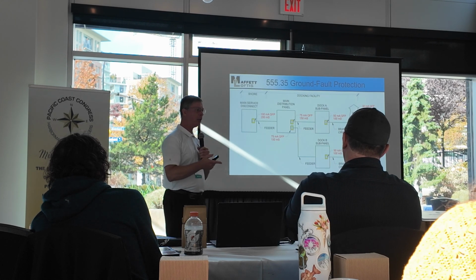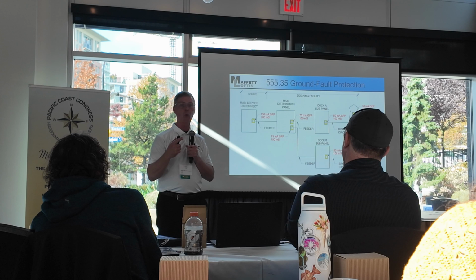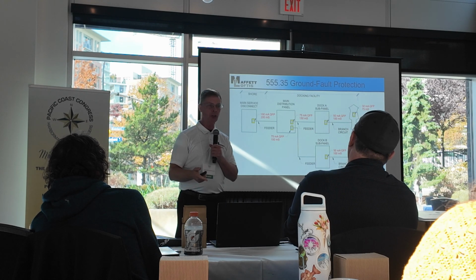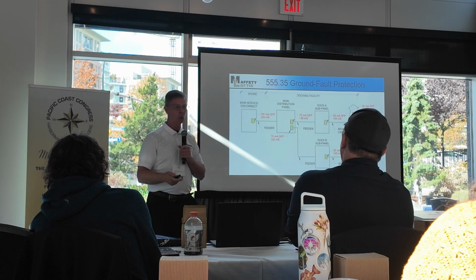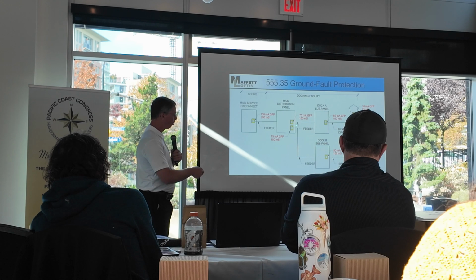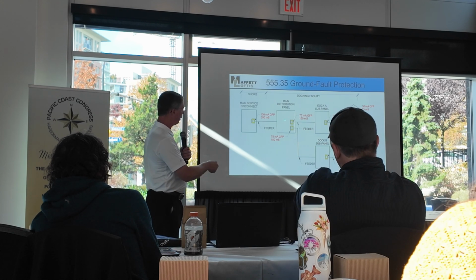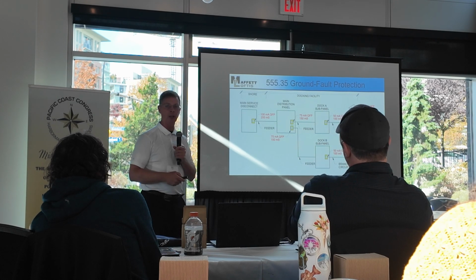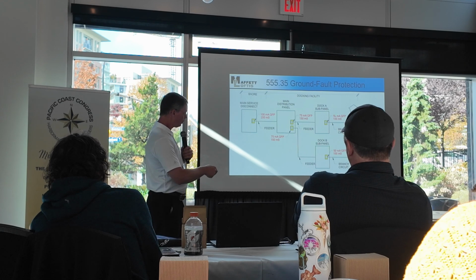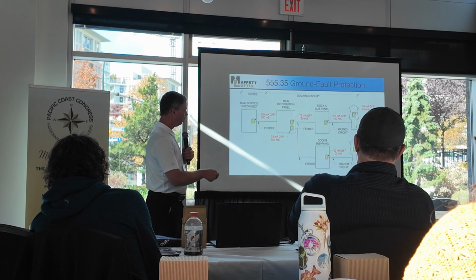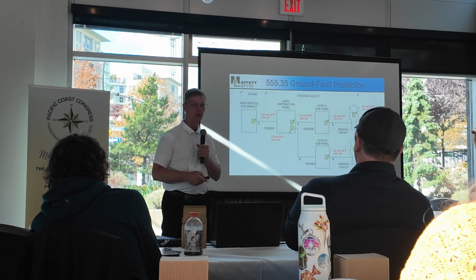Now this was permitted in the 2023 code, but it's going to be required in the 2026 code. That's going to be a requirement to have it fully coordinated. Now you could just do it here and up there, which is probably what we wind up doing, because you really don't need this intermediate, but this just gives you a graphic of what's going on.